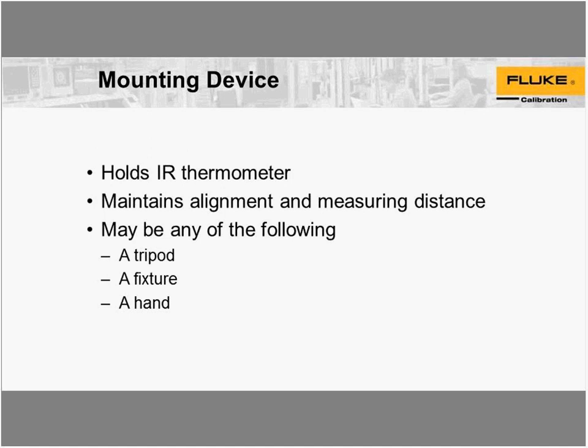The mounting device holds the IR thermometer. It can take one of different forms — it could be a tripod, some fixed ring that your laboratory comes up with, or it could be the human hand. If you have a big enough thermal radiation source, typically a manual calibration using your hand as a mounting device is good enough. If some technicians are very nervous or have trouble with trigger technique, you want to consider better fixturing. The mounting device maintains alignment between the IR thermometer and the thermal radiation source, and it also maintains the measuring distance.